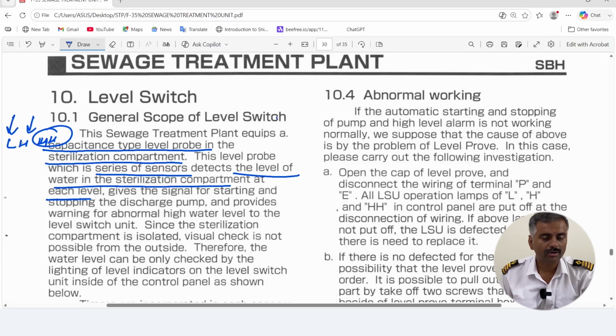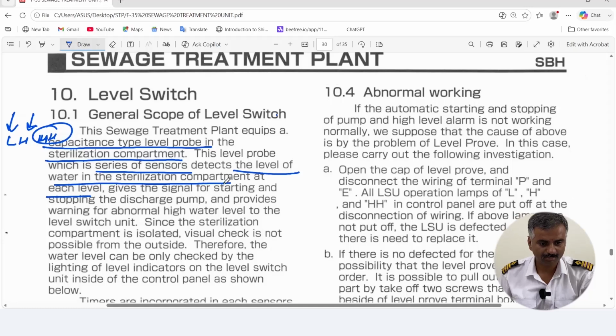Even if, say, you have unexpected discharge of water coming, or the pump is not able to pump out, in that case the water goes to high-high level. In that case you will have a high level alarm in the engine room. So that is the three levels, and the sensors are fitted on the capacitance type probe.